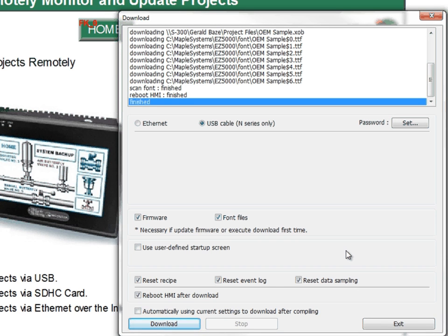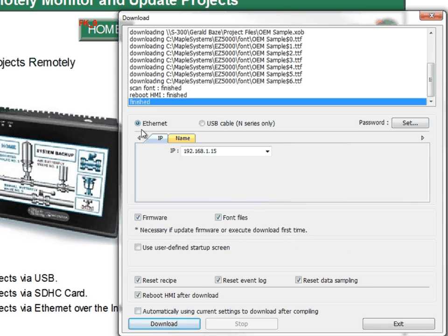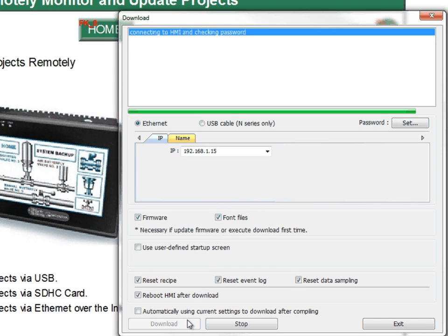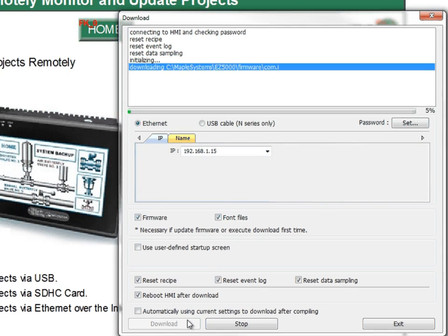Another way to download a project is over Ethernet. Whether over the internet or just locally, this is also an easy option. In the download window, check the Ethernet option and input the IP address of the HMI, then click download. Make sure the password for the project matches the download password in the HMI.